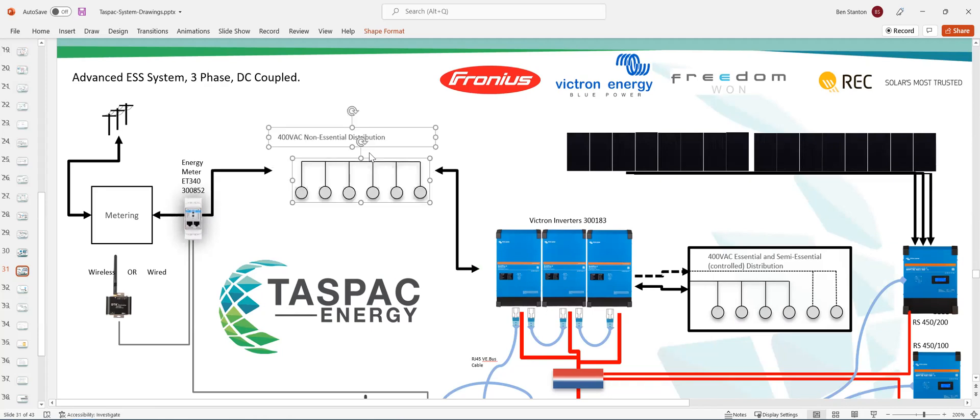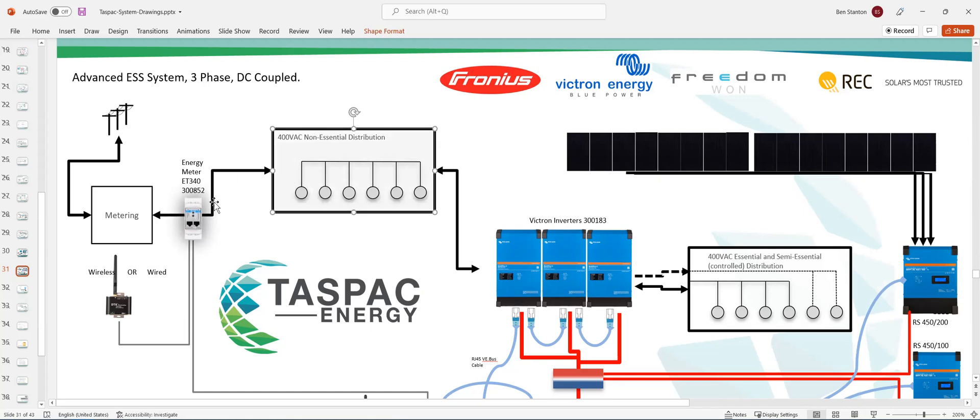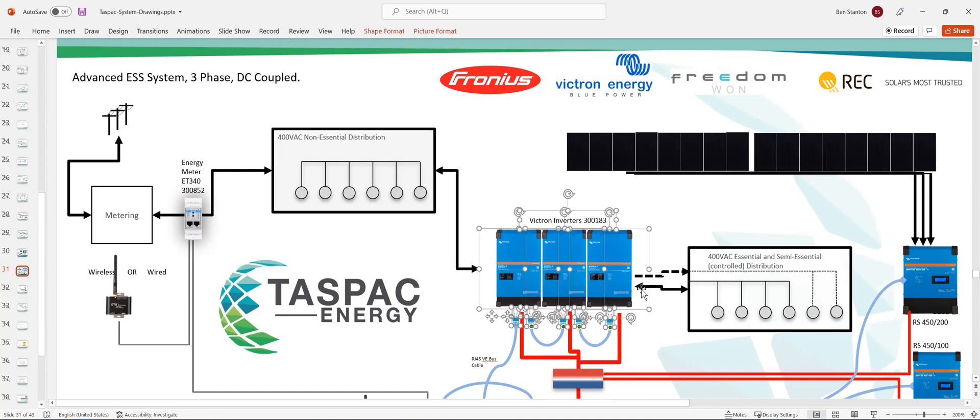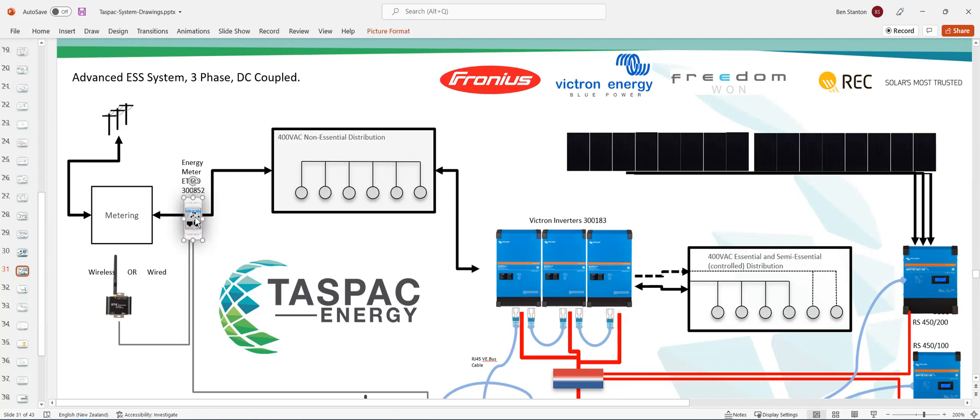So if you were going to have the non-essential board and split off some big loads, then what you would do is you would have the meter before all the three phases would come in before those non-essential loads. The reason for that is that these three inverters can keep providing, when the grid is connected, they actually can push energy back to the non-essential loads by gauging the grid point before those loads between the metering and the non-essential loads.